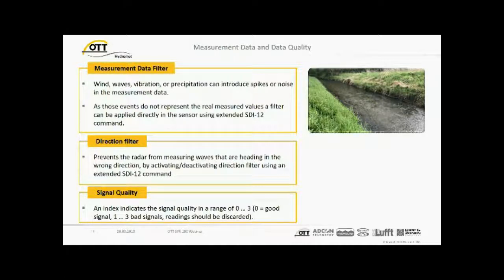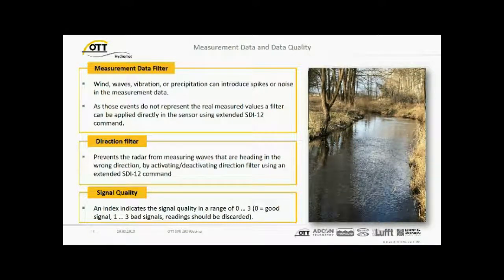Another example is if you have wind going against the flow direction. The main flow direction is the blue arrow here. The river is moving forward. Then wind comes and drifts the surface back on one side of the river. If the instrument is directly looking at this area and you have defined that you accept only outgoing flow, then the wind effect will be negligible, so it will be compensated. You will not see any erroneous measurements. That means we have a direction filter on board which prevents the radar from measuring waves that are heading in the wrong direction. You can activate and deactivate this with an SDI-12 command also.